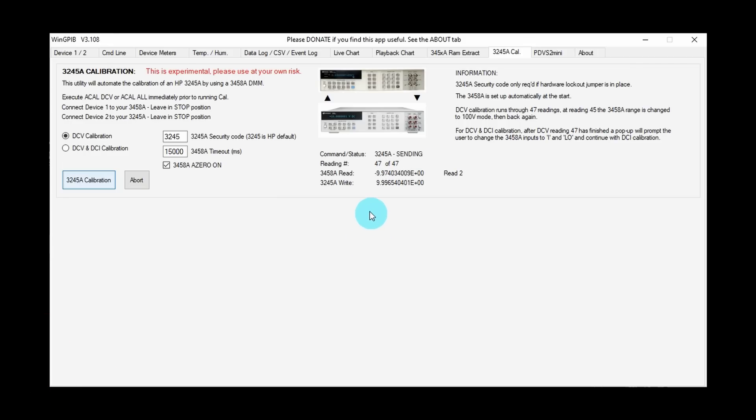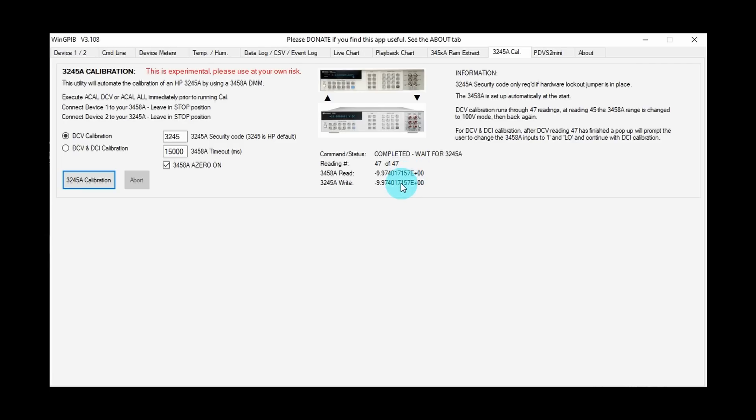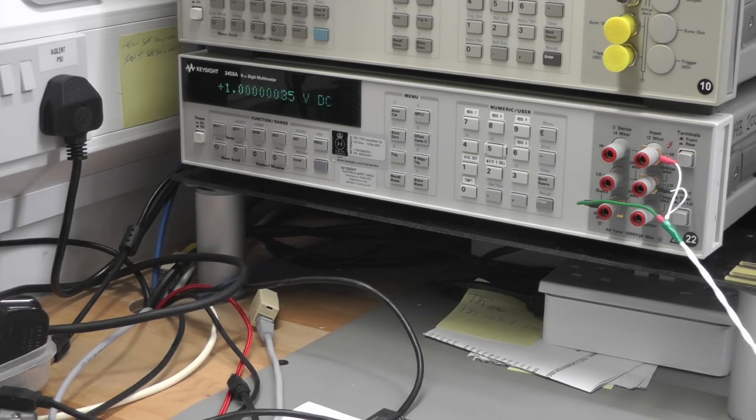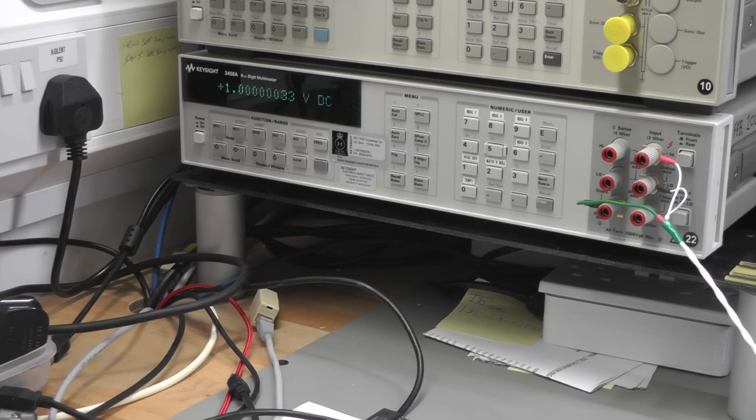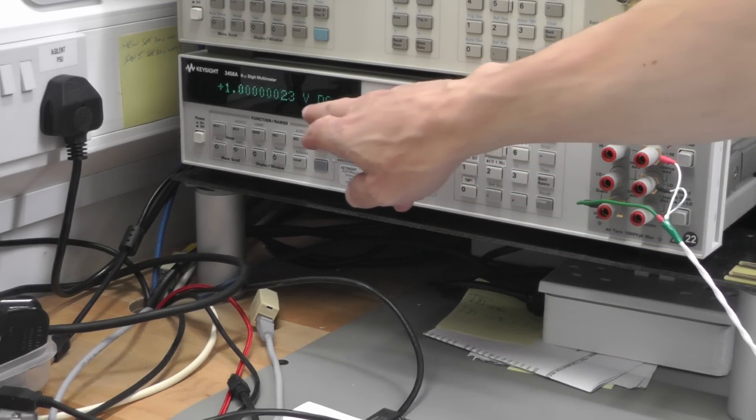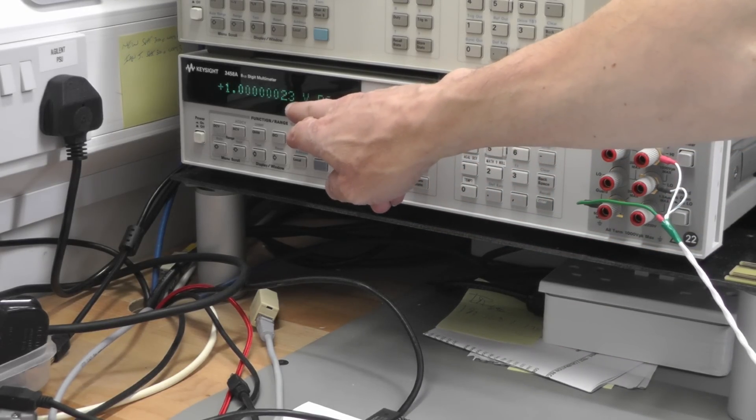And there we go, that's the last one just getting done now. Yep, we're completed and we're now waiting for the 3245A. The procedure is—the calibrating message is still on-screen on the 3245A, so we just have to wait for that to time out and clear. And at that point the calibration is saved. And there we go. You wouldn't have seen that happen off-screen. And there we go, after a quick calibration there you can see I've set the 3245A off-screen to 1-volt DC output, and you can see on the 3458A it's been recalibrated.